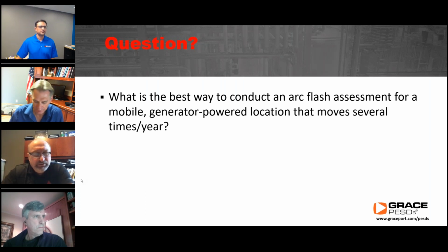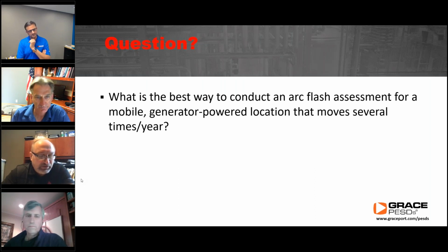So again, I was thinking about this one a little bit, and what I've discussed at times is, if you have a fixed generator as far as size, but your cable lengths could vary, you could do two things. You could do an incident energy analysis study for this system, and then you could look at the cable lengths and have a lookup table for cable lengths to the sub-distribution, and then have incident energy calculated at sub-distribution. That said, depending on the size, if it's a single generator or a large industrial construction site, then it starts to get pretty complicated, right?